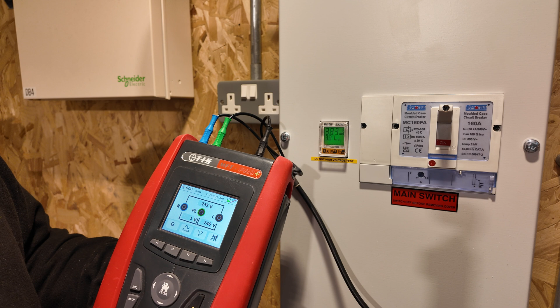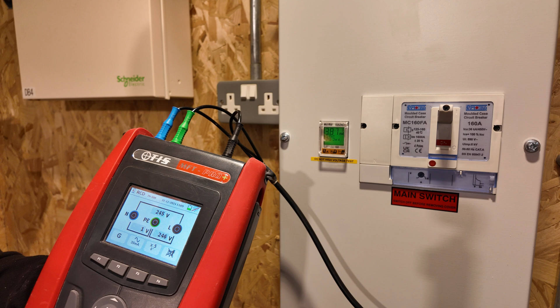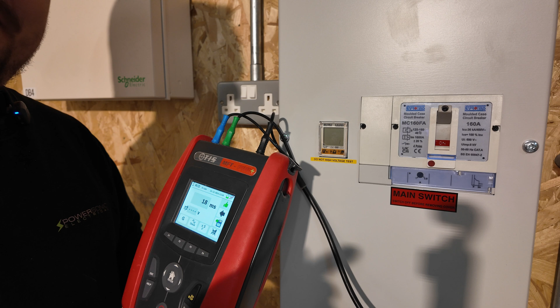Now we'll swing it over to 5 times, which will give us a big bump in milliamp leakage. 5 times 30 is 150 milliamps, so it should jump up to that level if I hit test. You can see it's done what I thought it would do, and it's taken out the RCDs in advance of this one and itself.